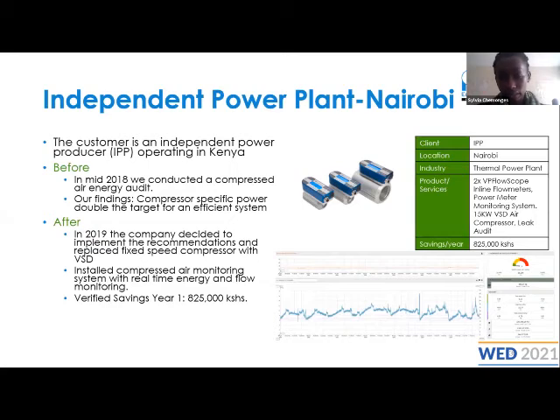So this is an independent power generation company. What they had was two fixed speed compressors. The energy they were consuming to supply compressed air, because they needed it for control air, that is for their instruments, was twice what would be required to generate the amount of compressed air they needed. So what we did is we carried out an energy audit.